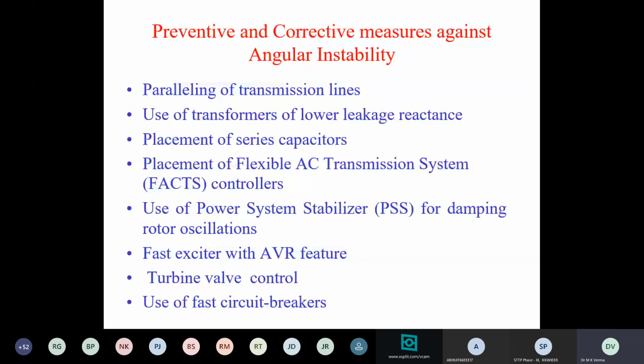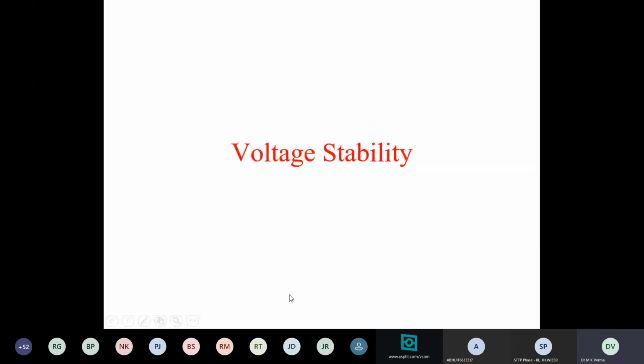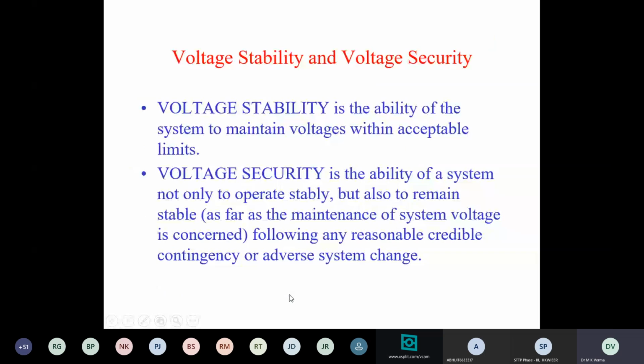That is, paralleling of transmission lines to reduce the reactance, use of transformers with low leakage reactance, series capacitors to enhance the power flow capability of the system, FACTS controller placement, use of PSS, fast exciter with AVR, turbine valve control, and fast circuit breakers. Then I talk about voltage stability, the ability of the system to maintain voltages within acceptable limits. And voltage security is the ability of the system to maintain voltages even under various contingencies or adverse system changes.